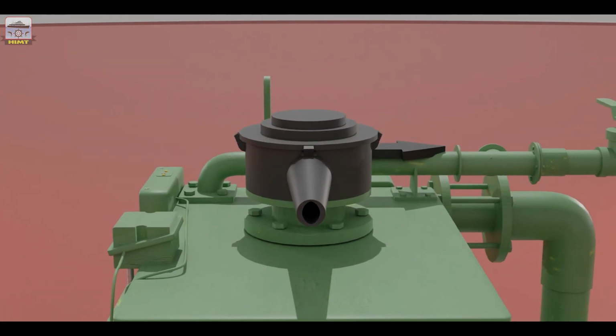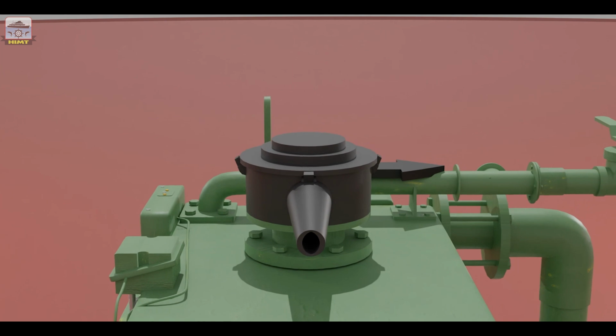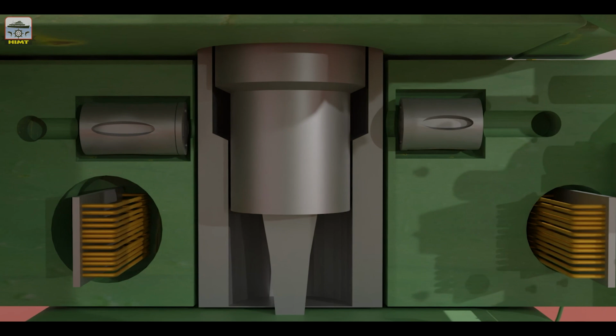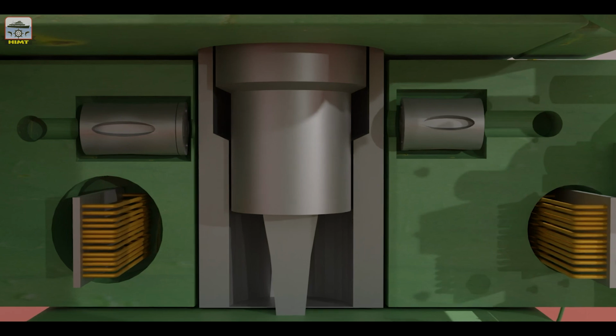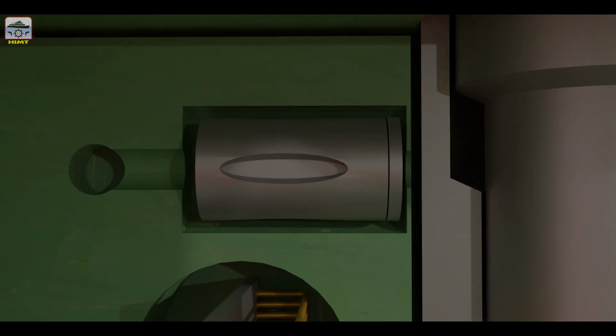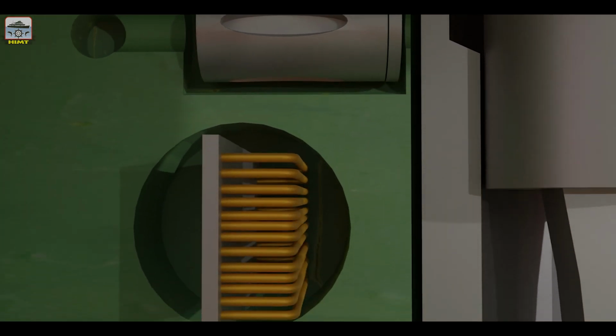It also has an air filter through which atmospheric air enters, and first stage suction and discharge valves located on the top of the cylinder. The air from the filter enters the cylinder through the suction valve and is discharged through the first stage discharge valve. The tandem type cylinder and piston arrangement includes a second stage suction valve and an intercooler.